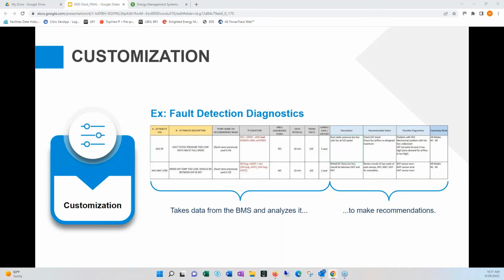Looking at the one at the bottom, AHU mixed air temperature low: the description is that the mixed air temperature should be between the outside air temperature and the return air temperature. This is actually very similar to what we discussed on day one about analytics software and its pre-built smarts and logic.